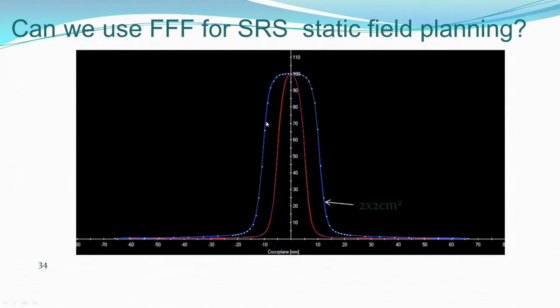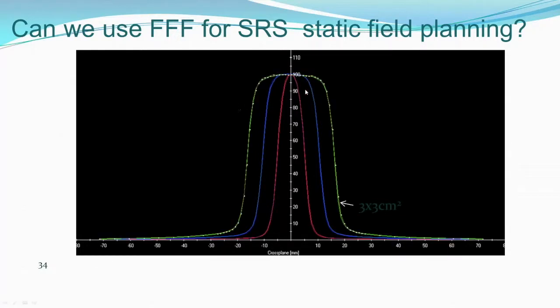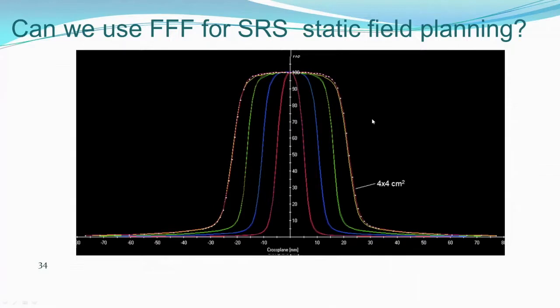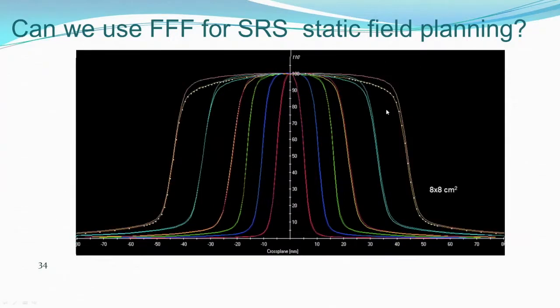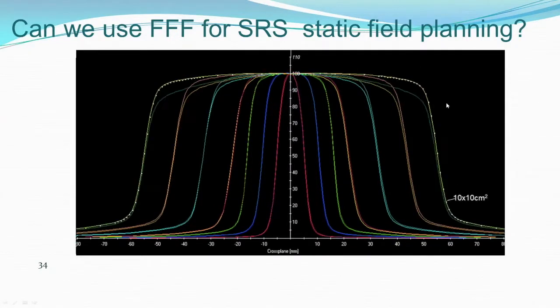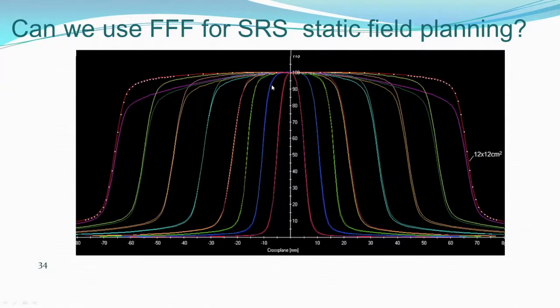And then I tried 2 centimeters. The triple F and double F profiles are overlapping. Went for 3 centimeters. It's a very small difference, but it's still almost overlapping everywhere. And when I went to 4, there was a slight difference, and at 5 and 6 a big difference, and the difference kept increasing. So as you can see here, up to 3 centimeters there is no problem. So we decided we can safely use the FFF beam for stereotactic radiosurgery with regular conformal beams. And the advantage we get is much less treatment time.